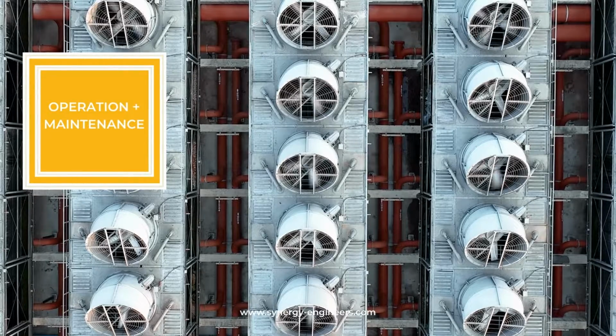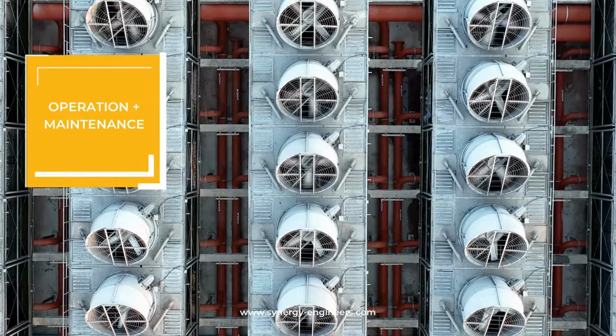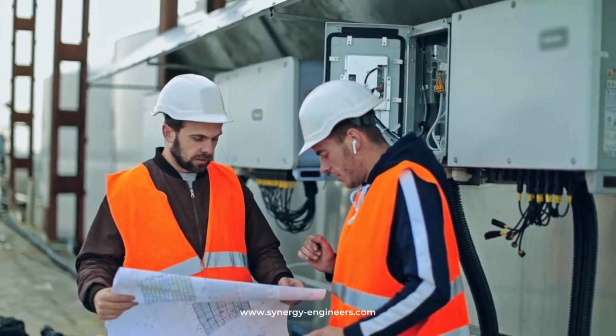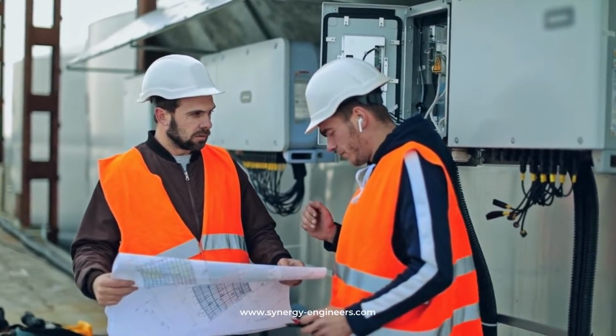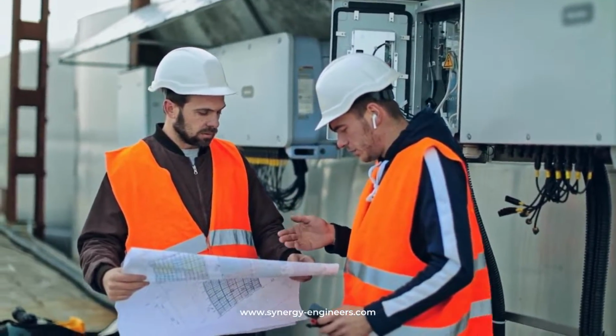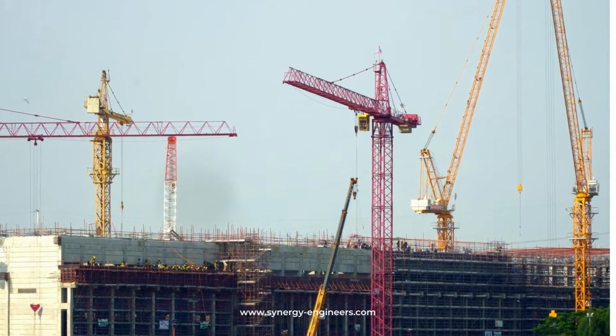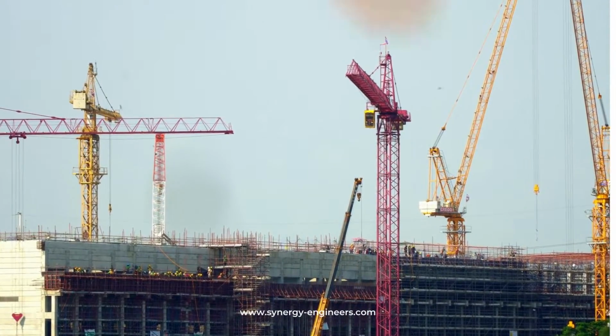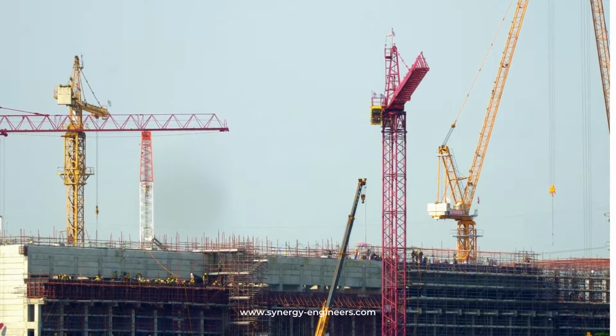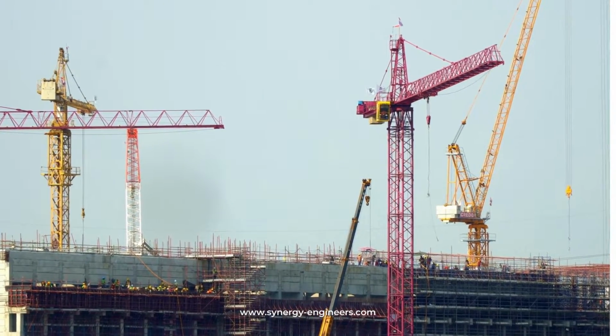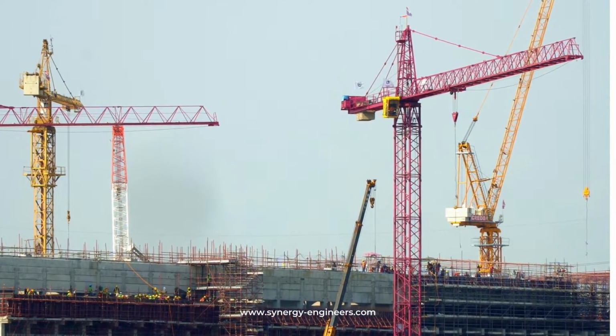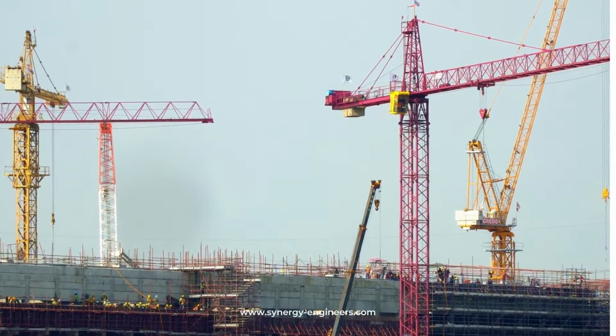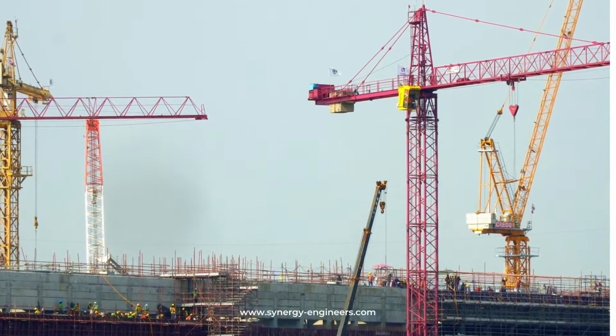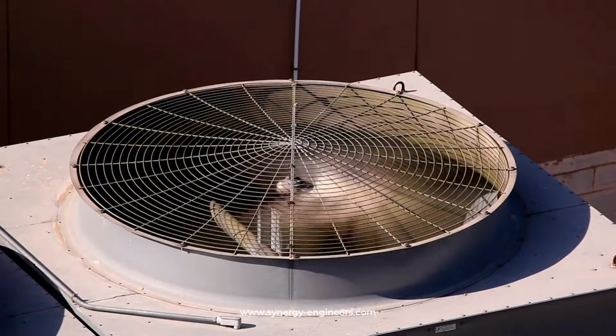With multiple smaller fans, the fan array is much lighter and easier to install and maintain without any big equipment. Most of these fans are at a weight and size that they can be carried by hand by one individual through a standard opening door. They don't require lifts or multiple people or a lot of labor-intensive effort to move parts and pieces in and out of that air handling unit to provide routine maintenance, preventative maintenance, or, in the event of a failure, replacement of that unit.